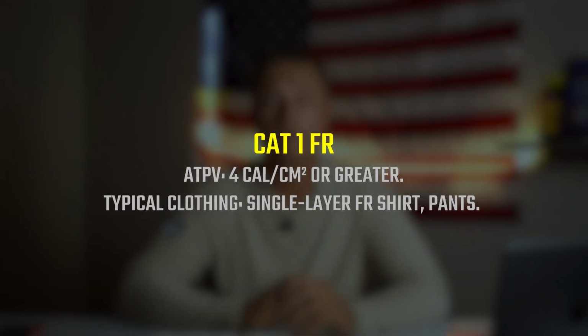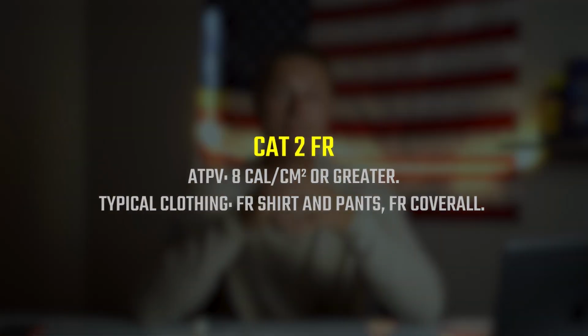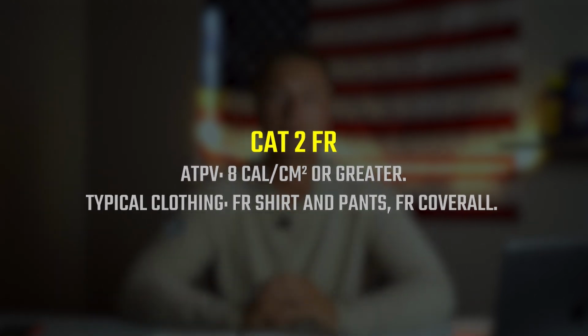A lot of shirts, pants, and sweatshirts have category ratings. You'll have category 1, which is a very base layer of FR clothing. They usually have an ATPV rating of 4 calories per centimeter squared or greater. This is typically just single-layer, thin FR clothing that you'd wear as a base. So typically, if you're working around energized sources, you're going to have to have something over that, because the minimum for us working around electricity is a Cat 2. Now, a Cat 2, like this, has an ATPV rating of 8 calories per centimeter squared or greater. And that's usually the bare minimum.